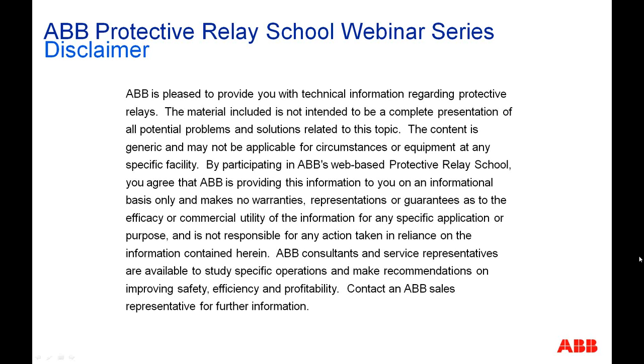Another question is that how we select these slopes in the characteristics. Well, normally the recommended slopes actually work quite well. In fact, in differential protection schemes, almost all the default settings can be set as they are, and in 90% of the cases it will work. But of course, if you want to change those slopes, there is an option for that, and you can actually change the endpoints as well as the slopes of the characteristics, and it depends upon your power system requirements.